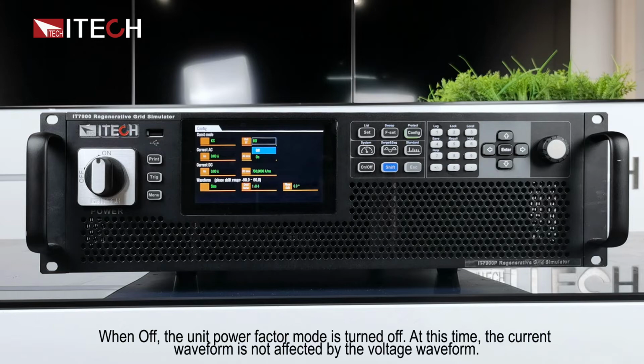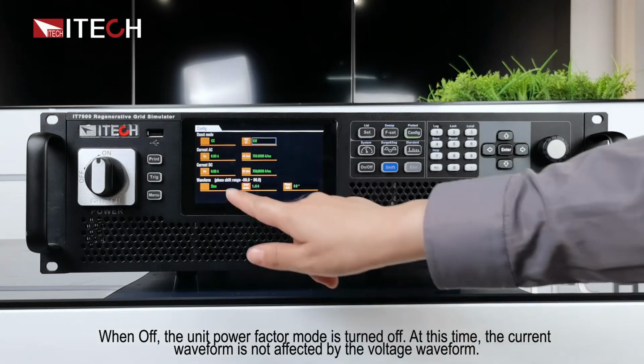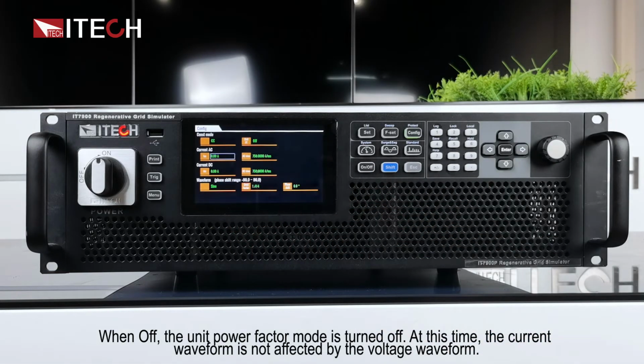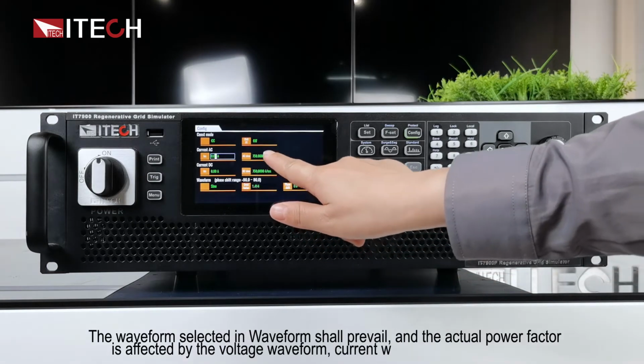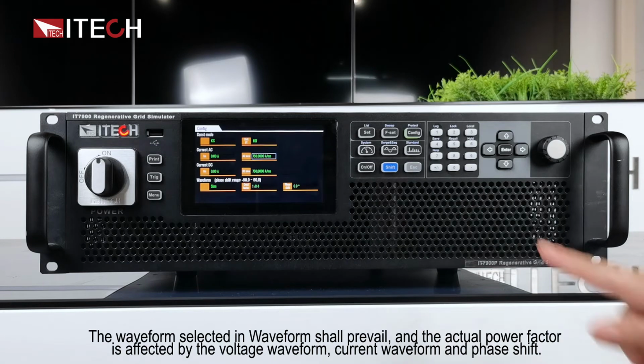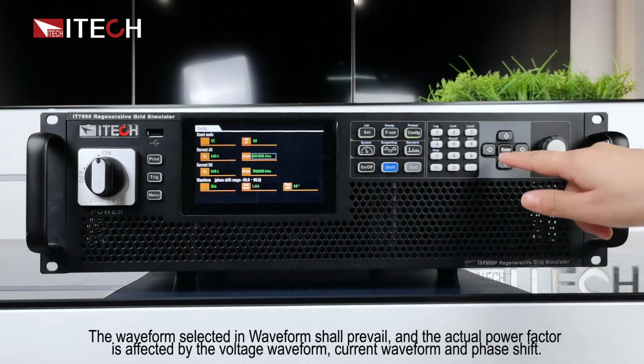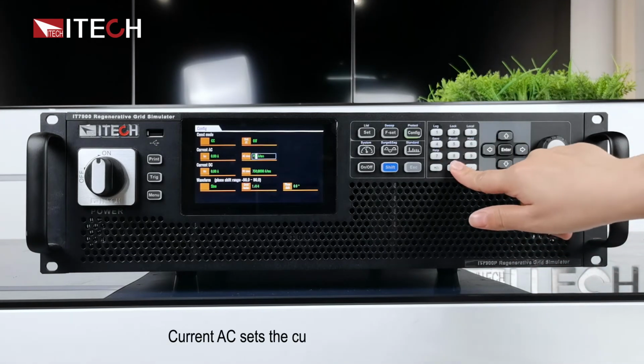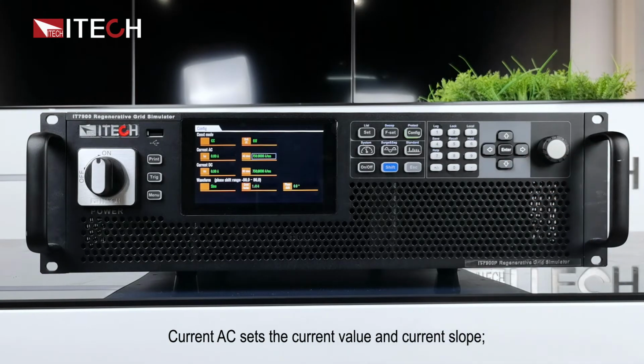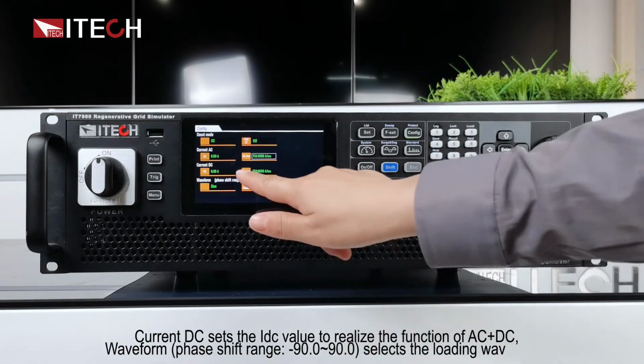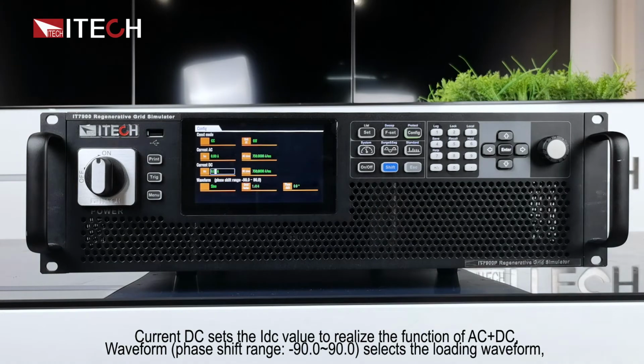When off, the unit power factor mode is turned off. At this time, the current waveform is not affected by the voltage waveform. The waveform selected in waveform shall prevail, and the actual power factor is affected by the voltage waveform, current waveform, and phase shift. Current AC sets the current value and current slope. Current DC sets the IDC value to realize the function of AC plus DC.